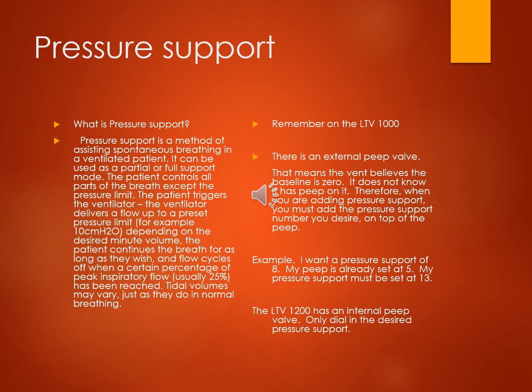All right, next one. So again, pressure support can be its own mode, and it can be an adjunct to a mode. One of the things to think about now, hopefully you won't see most of these, but your LTV 1000 has an external PEEP valve. Oh my goodness, what does that mean? The PEEP valve is something that you dial in on the end of the circuit, on the exhalation side. So it does not internally view PEEP. So you have to actually dial that in and set it, and then remember that when you're adding things like pressure support, the pressure support doesn't know that the PEEP is there, so you would have to add that on top of that.